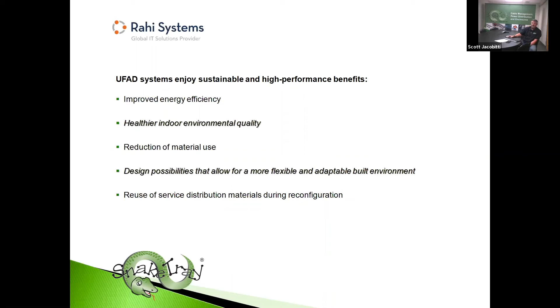The whole idea of flexible use within a raised floor is being able to move people around within that space, and we're going to see more of that as more people come back into the work environment. That means we're reusing those components—if the duct has to be moved, we're trashing it, we're not going to utilize that. Floor tiles and diffusers, we can move and reuse during the reconfiguration process.